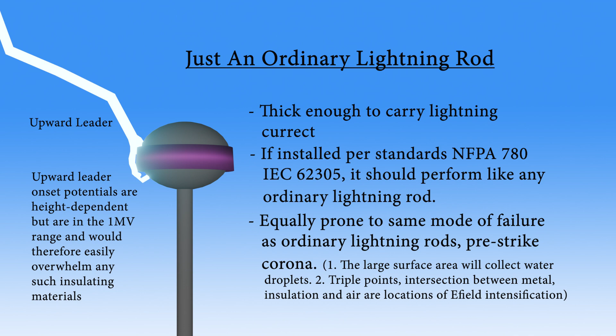Based on all the available information, under lightning storm conditions, these devices should work like any ordinary lightning rod. Its promoted design features would have no effect on the probability of a direct strike. However, since it is a piece of metal of adequate thickness to conduct a lightning current, and if it's installed in accordance with standards like NFPA 780 and IEC 62305, it should collect and conduct lightning strikes to ground with similar efficacy as any code-compliant system.